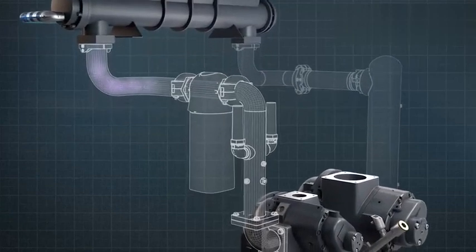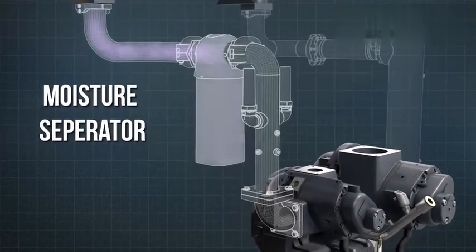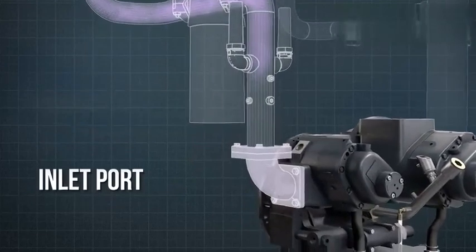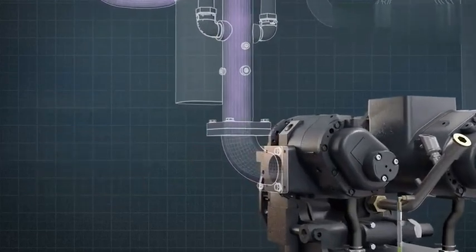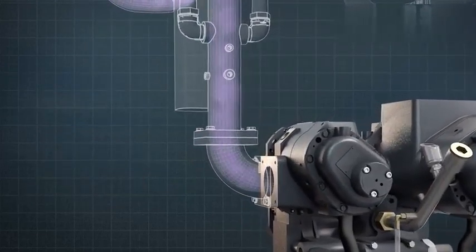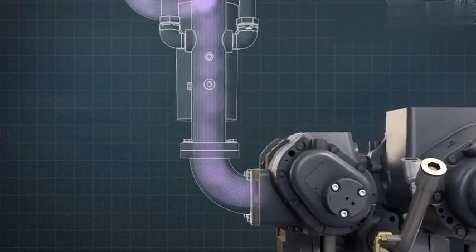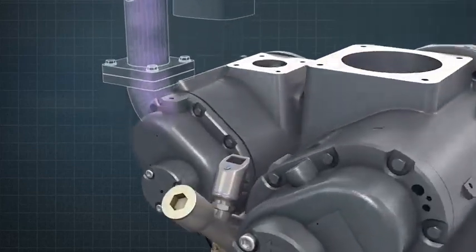The cooled compressed air passes through a moisture separator, then onto the inlet port of the second stage rotor. The volume of the air is greatly reduced after first stage compression, which means that the size of the second stage rotors is much smaller.